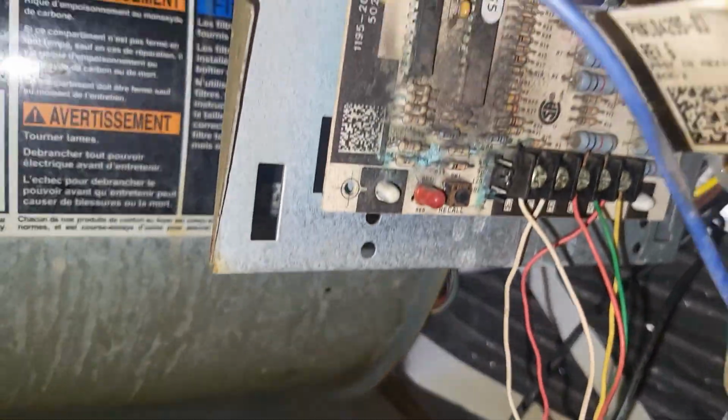Guys, that thermostat up there is set to 72 and it's at 50 degrees, and that's a non-programmable thermostat upstairs. And according to the tenant, this unit has been off for the past couple of days. But the good thing about these Ducane furnaces, you can see, even if it's currently working, we can see the last 10 system faults. So this helps us out in this scenario.